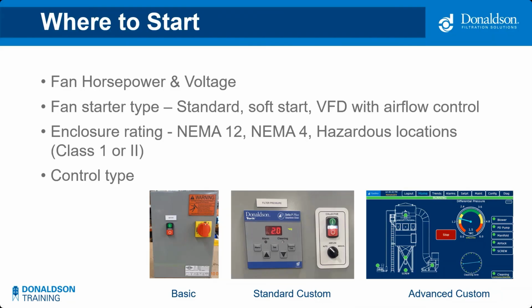The enclosure rating of the box itself, is it NEMA 12? When the control panel is located indoors with more standard temperature and humidity conditions, somewhere between 32 and 90 degrees and up to 85% relative humidity. The NEMA 4 for indoor or outdoor use produces a degree of protection against the elements, or is the control panel in a hazardous location?